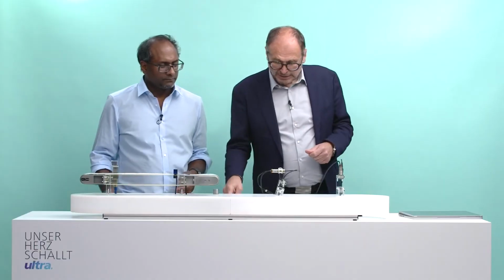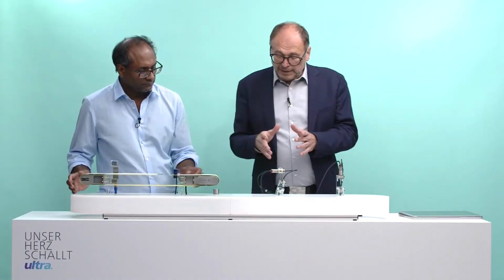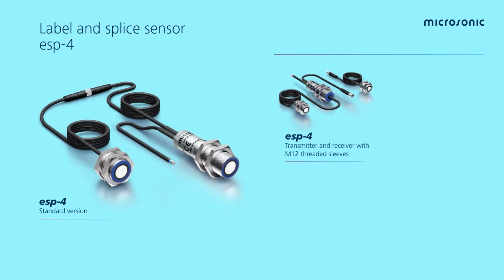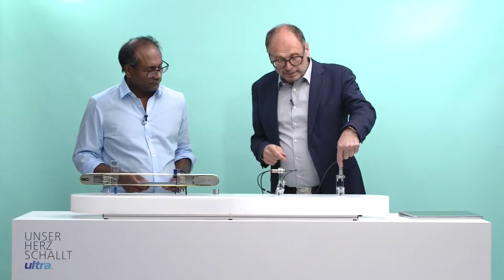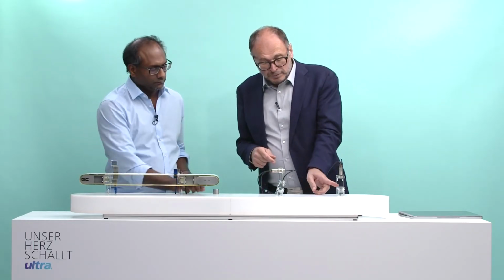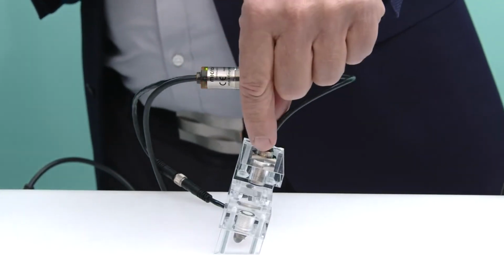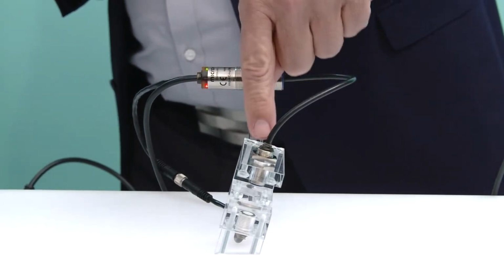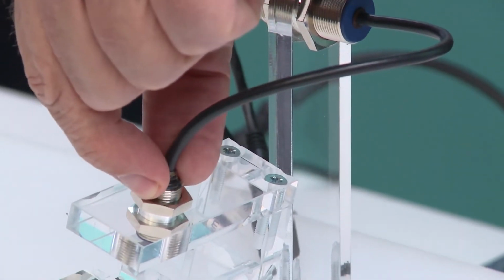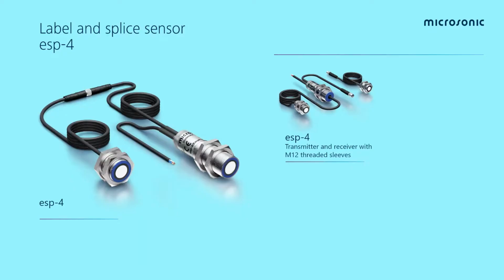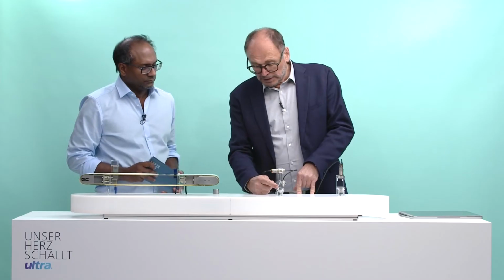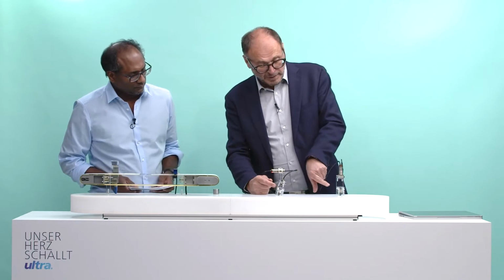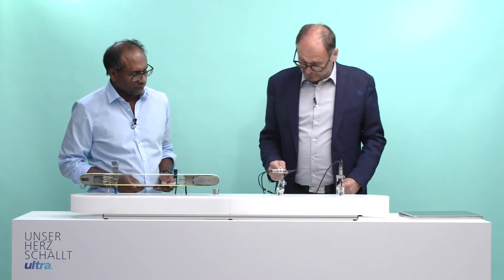We have 2 housings. We have the standard housing, which looks like the standard dBK+4, meaning receiver and electronic in one thread and below the transmitter. Here we have built up the sample with M12 housing. These transducers are smaller than the M18 transducer, and their frequency is higher. This one is 500 kilohertz ultrasonic frequency, and this one is 400 kilohertz ultrasonic frequency.